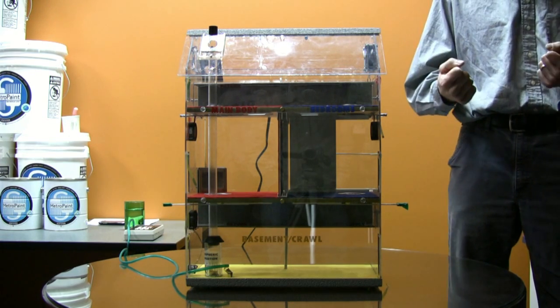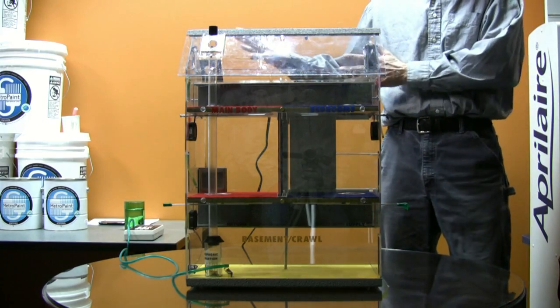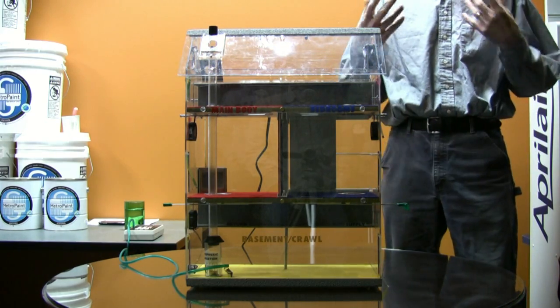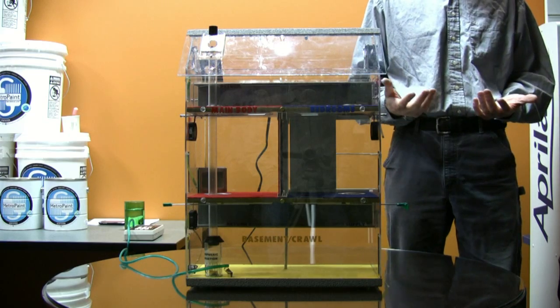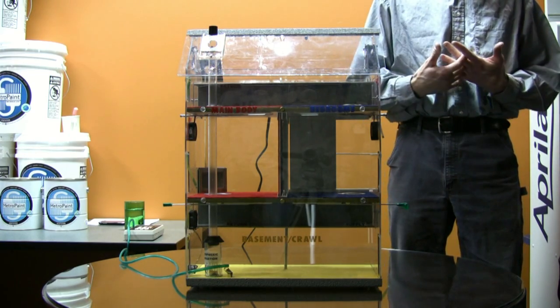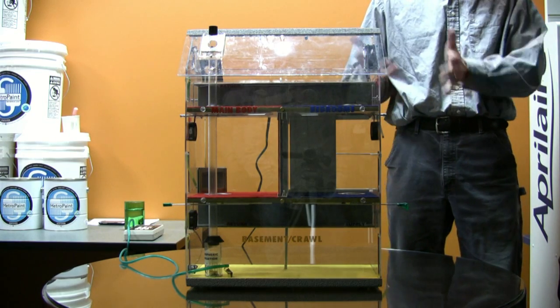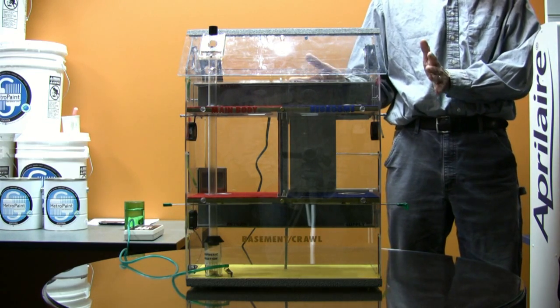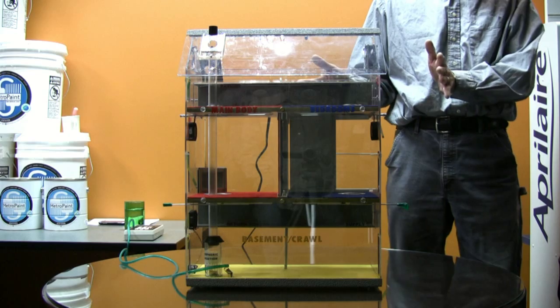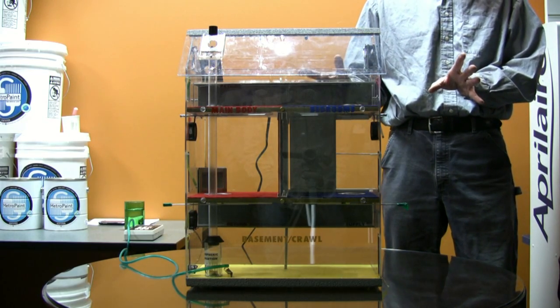And that's not good, because when you backdraft it, all the exhaust gases that are supposed to be outside are inside. That's when you typically have carbon monoxide poisoning in a home. Every winter, 1 or 2 families in the Northwest die because their equipment is backdrafting. This can help you understand why that can take place.